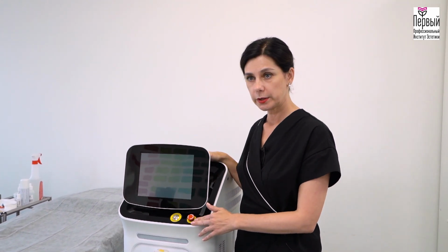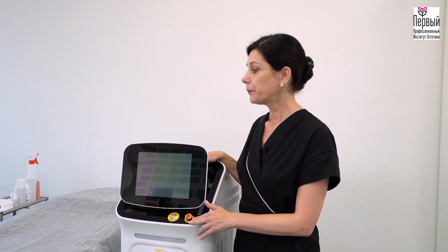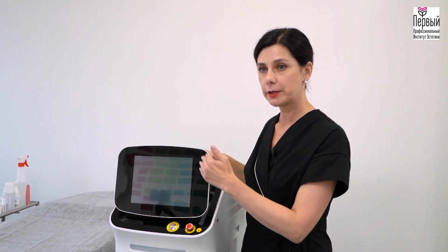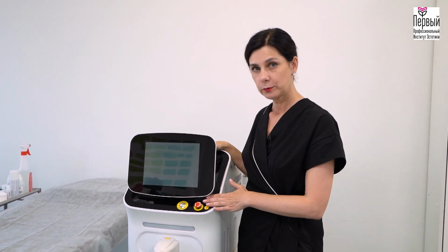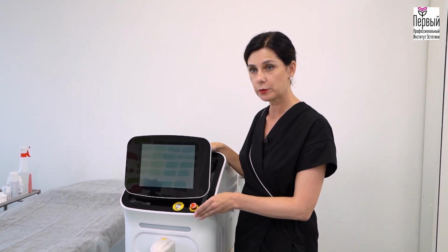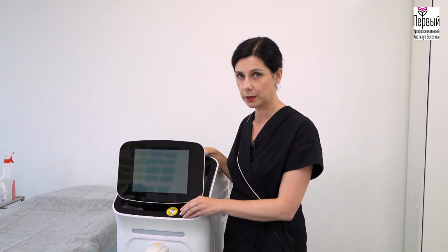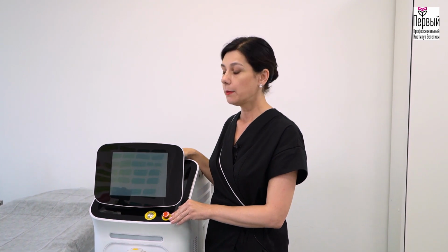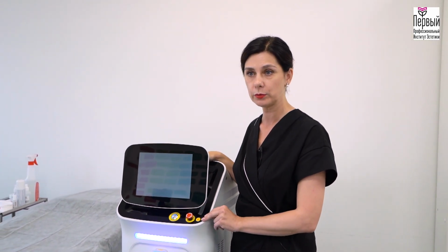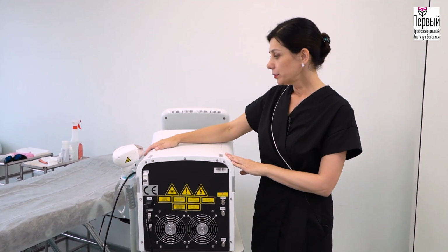It can automatically help us select the parameters and perform the self-test all the time. That's why we can see those icons. When you move the device, it can also disable itself. It will feel the vibration and this button will be automatically activated even without pressing it. This is why inexperienced users will always get confused when they switch the device on, but it does not start. Just check the lock button and press or turn it so that the device can restart.